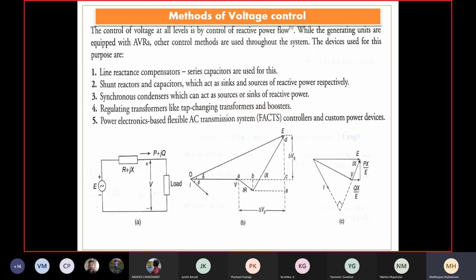So therefore, the system which is delivering power to the highly inductive system, which is overcompensated or compensated, now becomes highly overcompensated if we are not going to eliminate capacitors immediately or in a systematic manner. Therefore, to compensate that, shunt reactors are preferred. It means reactors absorb reactive power and capacitors supplement reactive power. By compensating these with systematic switch off and switch on by the adoption of technology, we can definitely manage the reactive power in the system.